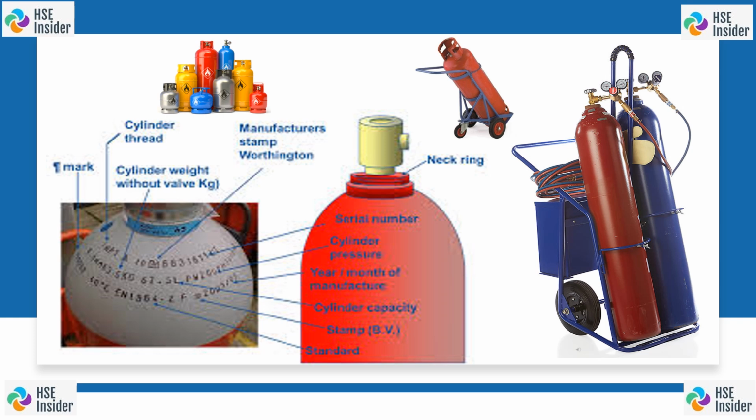Then come to the important point of handling and use of gas cylinders. When handling, the cylinders shall be adequately supported. Trolleys and cradles of adequate strength shall be used when moving the cylinders. The cylinders shall be handled carefully and not be allowed to fall upon one another or otherwise be subjected to any undue shock.